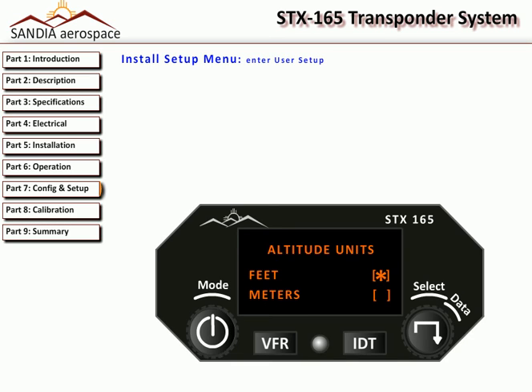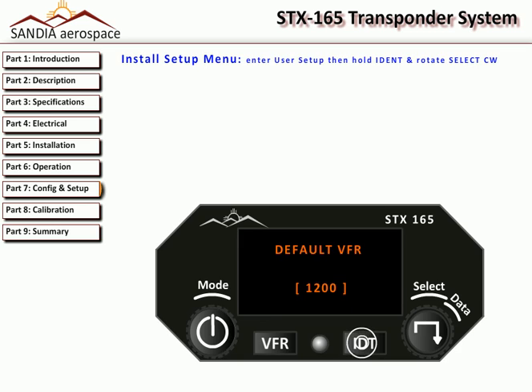Once in the user setup mode, you can enter the install setup mode in a similar manner. First, scroll all the way to the last page, which is the default VFR code page. Now we will again hold the ident button while we rotate the select knob, but instead of going counterclockwise, we are going to rotate clockwise until you feel a hard stop. Continue holding the ident button and hold the select knob against its stop for 3 seconds or until you see the pressure altitude trim page. This page is used for calibration, which we will get to later.